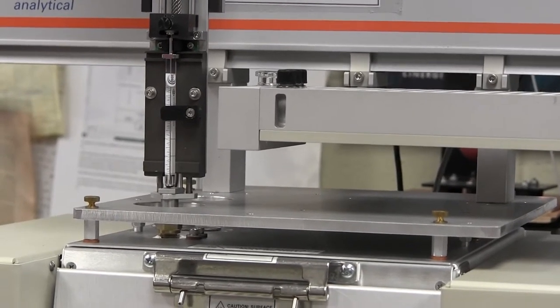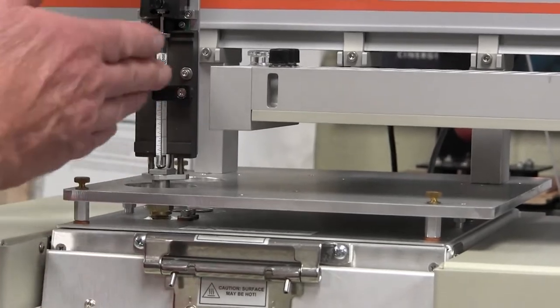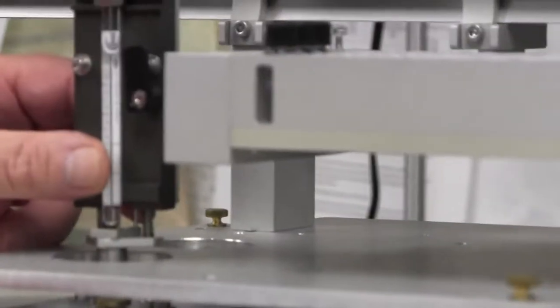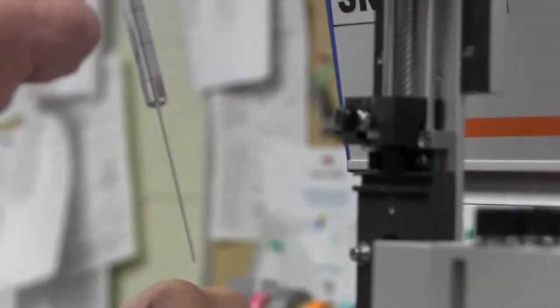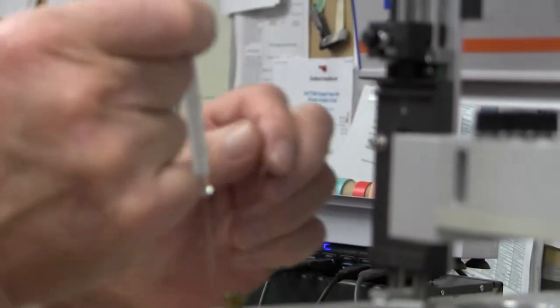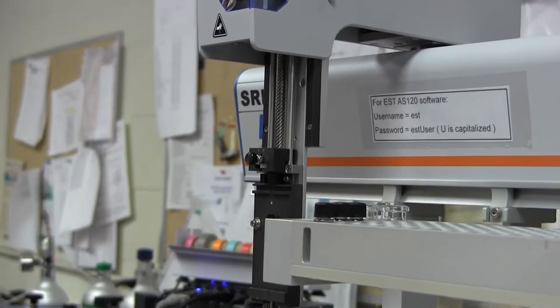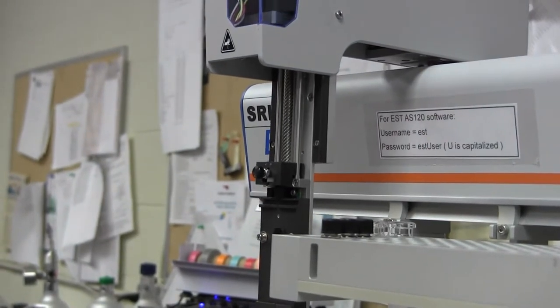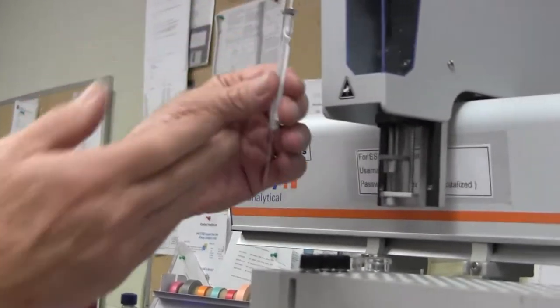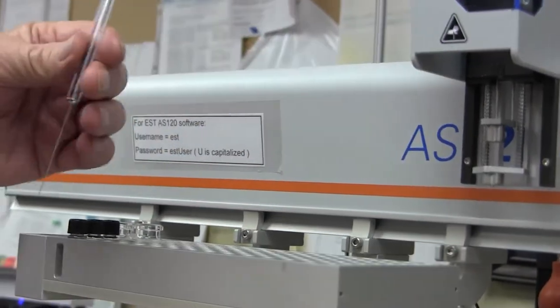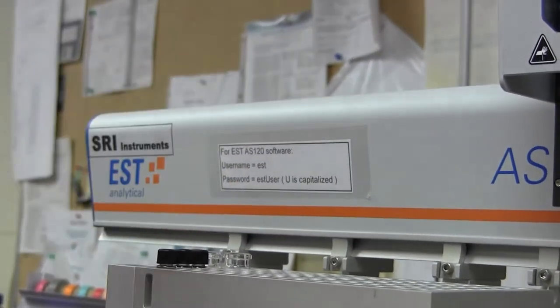But this is also a convenient way to put a new syringe in or take an old syringe out. So I'm going to take this syringe out, turn this little grip thing and then loosen this nut. I'm going to pull the syringe out and because the syringe needle is in the injection port it's easy for me to get it in or out. You can see the syringe retracts up into this housing and then goes over to here. So this is just a convenient way of getting the syringe in and out.